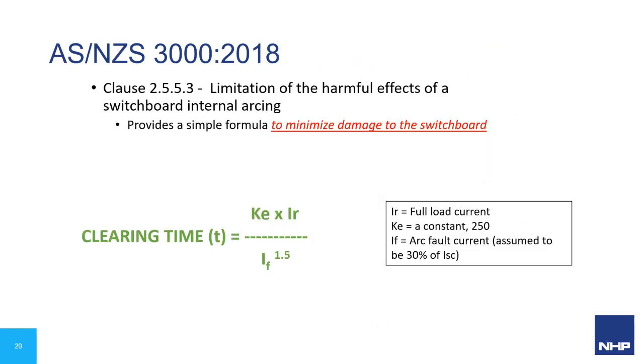AS3000 gives us some recommendations as well, but the important part about that is this is a formula to minimize damage to the switchboard. So it's basically a constant times the rated full load current divided by arc fault current to a power. It's saying to assume that arc fault current is 30% of the short circuit current. So again, this is to minimize damage to the switchboard. It's not really about operators.